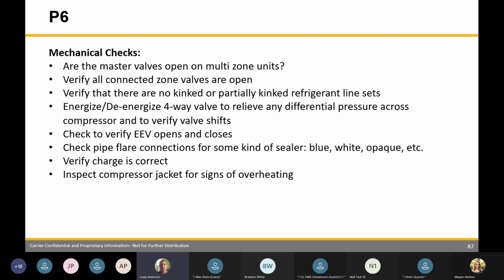Other things to check for mechanical checks, like I told you at the start, our units have master valves and then each zone has its own valve. They all need to be open. I've been to job sites. I drove 3 hours and got there and they didn't open the little valves all the way. They opened the main valves, but they didn't open the other 2 valves all the way. They just cracked them. So they were getting poor refrigeration flow to the units. So make sure they are all totally open.